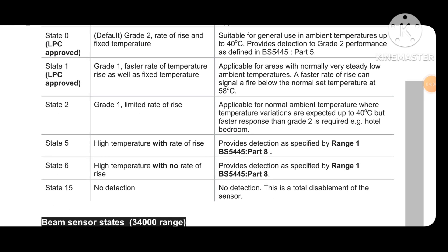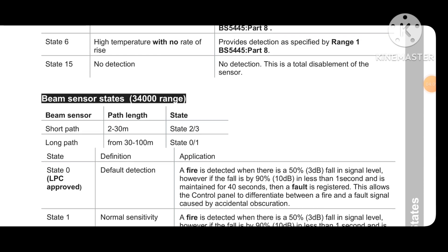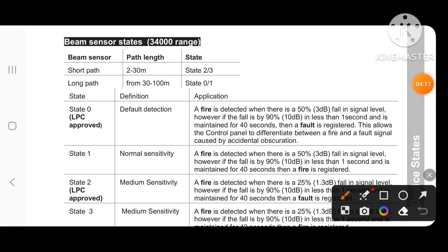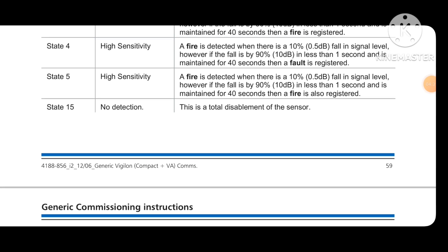For beam sensors: short path (2 to 30 meters) uses state 2 or 3; long path (30 to 100 meters) uses state 0 or 1. State 0 is the default detection — fire detection. State 1 is normally used likewise. If you put state 15, it means no detection, and the device will show a fault of invalid configuration.